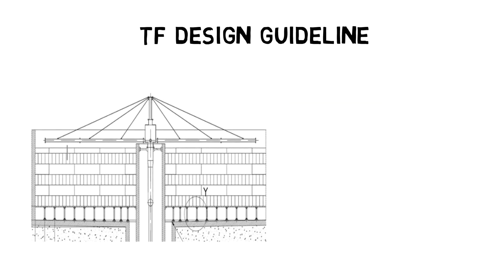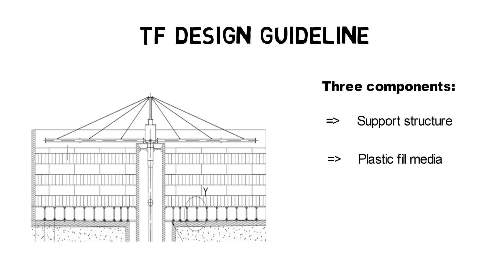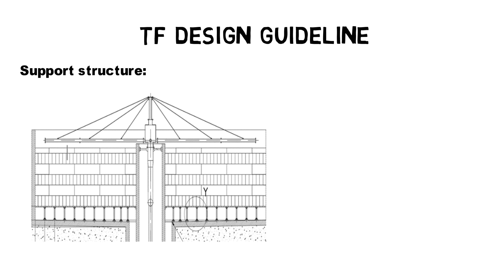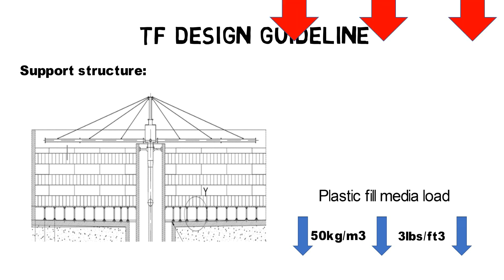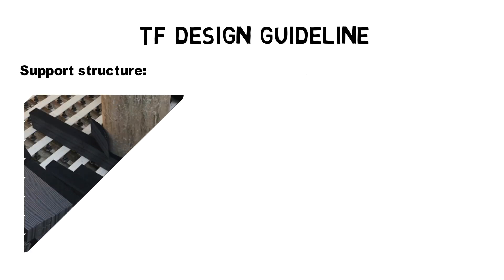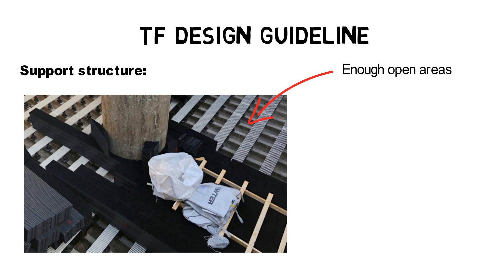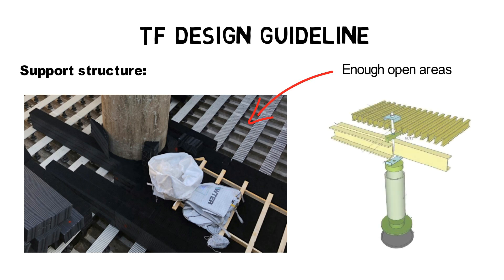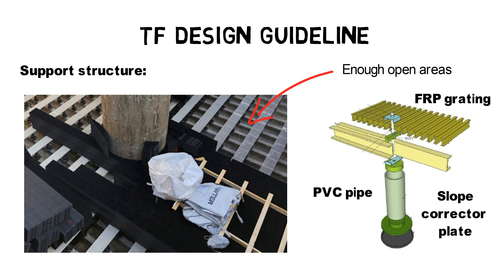For the design of trickling filters, three components are very important: the support structure, plastic-fill media layers, and the rotary distributor. The support structure has to withstand high vertical loadings of up to 50 kg per cubic meter (3 lb per cubic foot) of plastic-fill media, plus up to 250 kg per cubic meter (15 lb per cubic foot) for attached sludge and water inside the fill media packs. At the same time, the supporting structure must leave enough space for sludge collection and removal and to avoid blockage of plastic-fill media channels. Therefore, the support structure typically consists of PVC stanchions, FRP grating, and slope-corrector plates to adjust for bottom slopes.